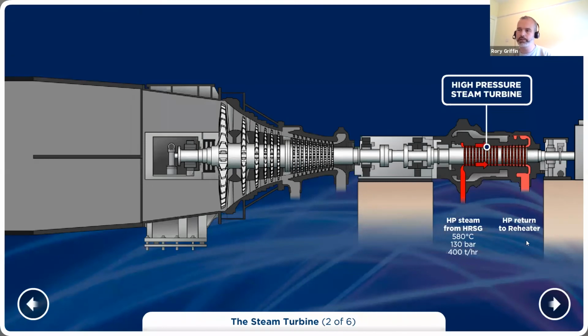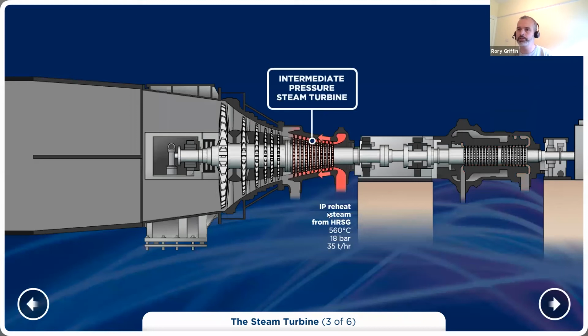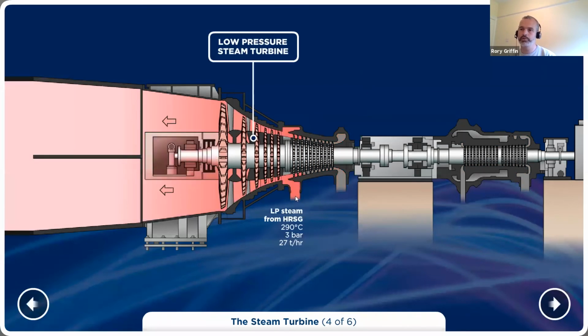At this point, we actually send this back to the boiler, to the reheat sections, and it joins with the IP superheated steam. So you have about 330 tons here. You'll have about 30 tons of IP, and once it comes out of the reheater section, it then comes back down as IP inlet. Now, again, apologies, these figures are a little bit wrong. The IP contribution on its own is 35 tons per hour, but you have to bear in mind it's actually joined up with the exhaust of the HP turbine. So it's this plus 330. So there's actually about 360 tons of steam per hour heading through the IP cylinder. And from here then, the LP steam comes in, which, you know, close to 30 tons per hour. So you're up to nearly 400 tons per hour of steam passing through into the exhaust of the machine.